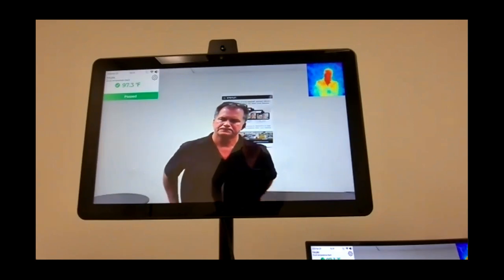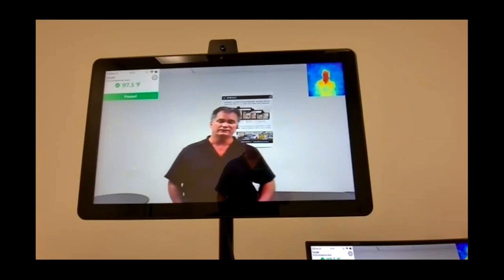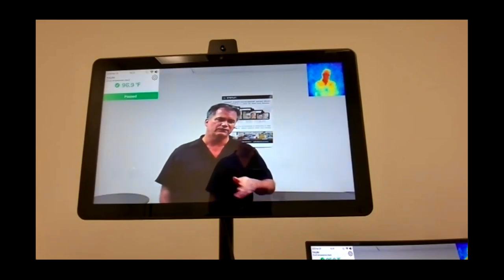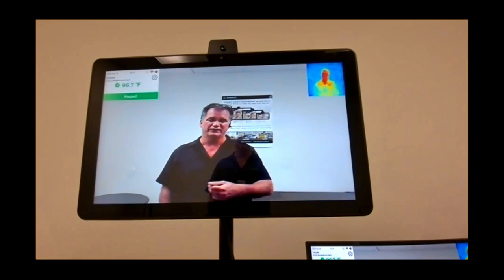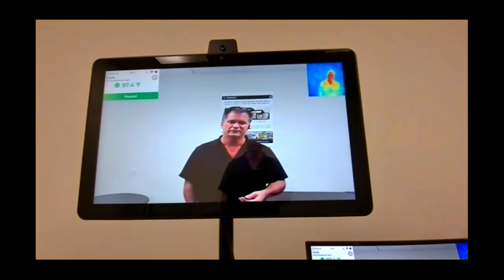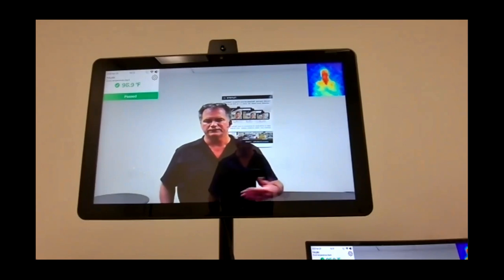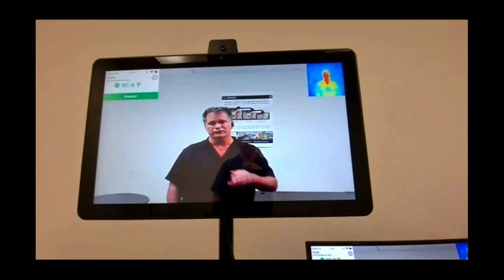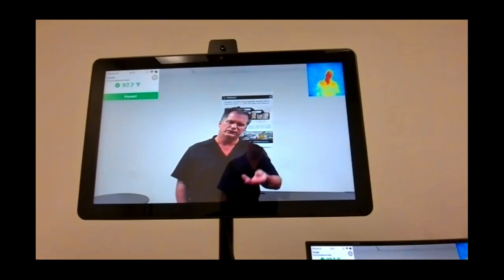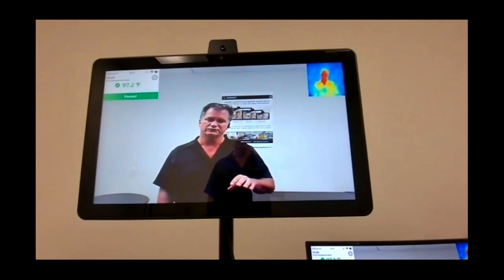Question: do email or text alerts work out of the box or do they require additional hardware? That is all firmware — no additional hardware. Today you have the basic app functionality shown here. Through a future firmware update, once we have the REACTS engine available — likely two to four weeks — you would go through the setup pages, do a system update, and then configure email parameters, including where those messages are directed.